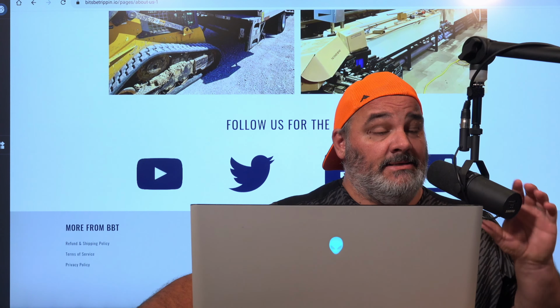The WhatsMiner, they've done okay with the heat, but we seem to go through a lot more control boards than anything else on WhatsMiners, and power supplies. So they handle the heat, but then they also burn through equipment faster, it seems. So that's just our own experience, and that could be just because a lot of our deployments have to do with containers, and there's differences between containers and building designs.